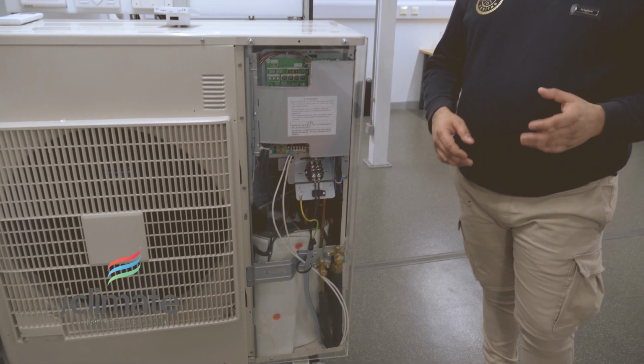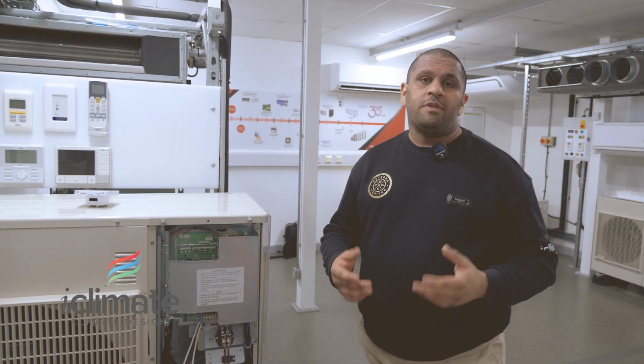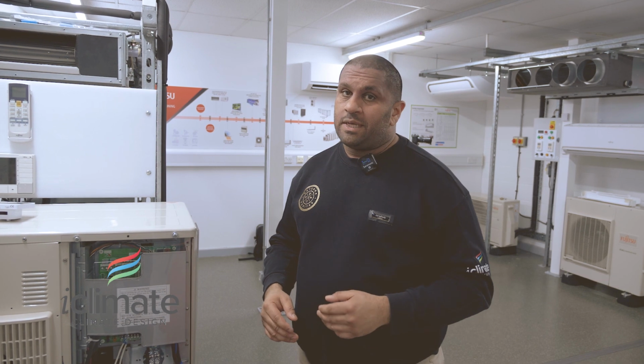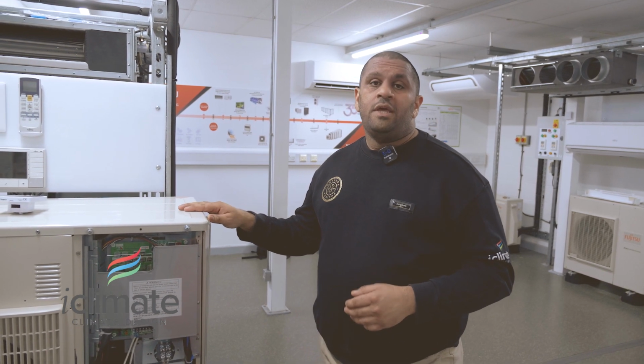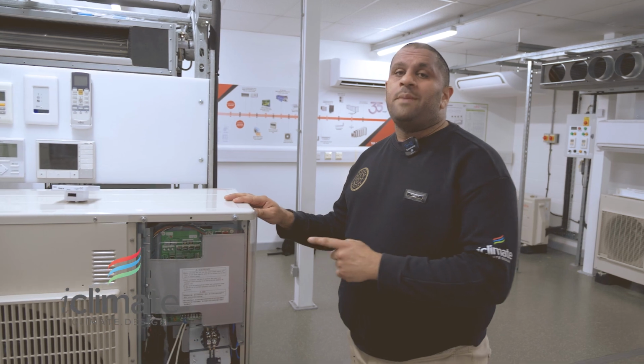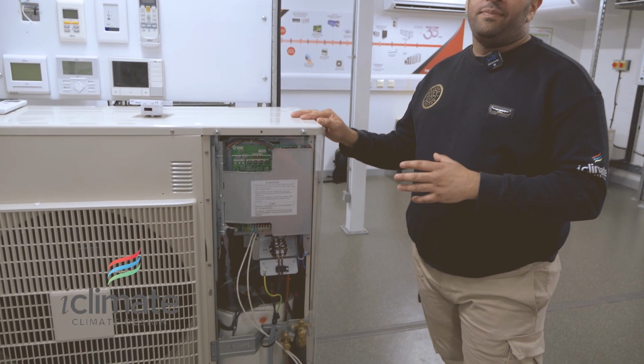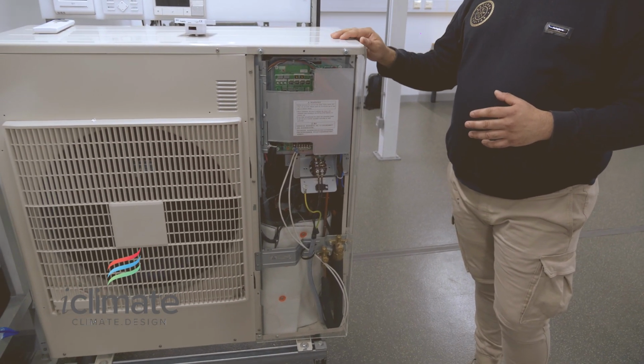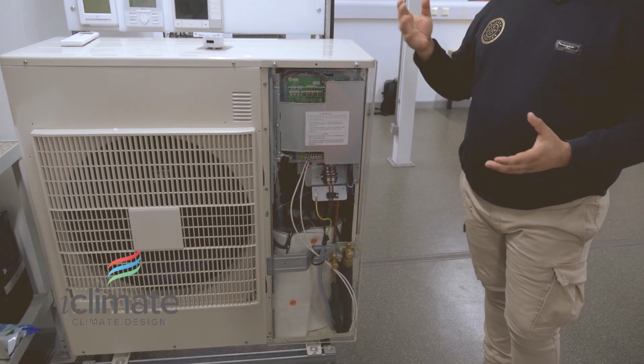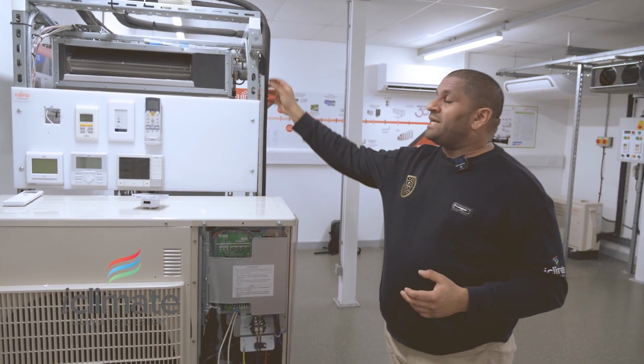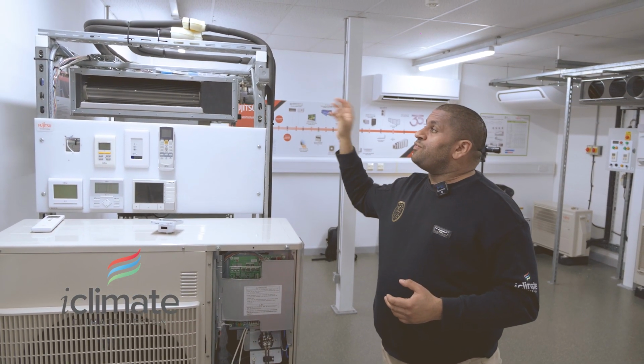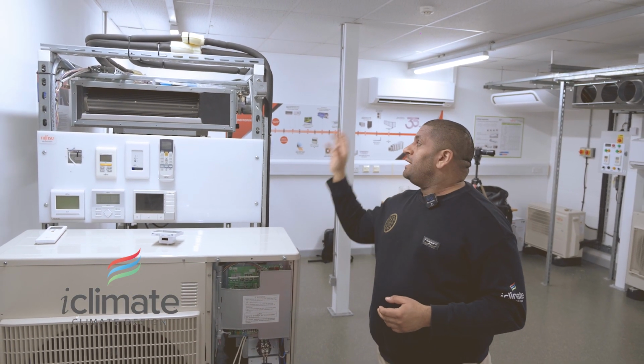Let's talk power supplies. So for a split system and a multi-split system, the power supplies all go to the condensing unit. So you need one point of power from your premises to the outdoor AC condenser. We then bring that power supply back and feed the associated indoor units through our interconnecting cabling. But when it comes to the VRF system, you need two power supplies. So the outdoor condensing unit must be on its own dedicated power supply, and the indoor units need to be on their associated dedicated power supplies also. So you need to balance the fact of, do I have one set of pipes on the outside of my property, and am I okay to run independent power supplies for each of the indoor units?